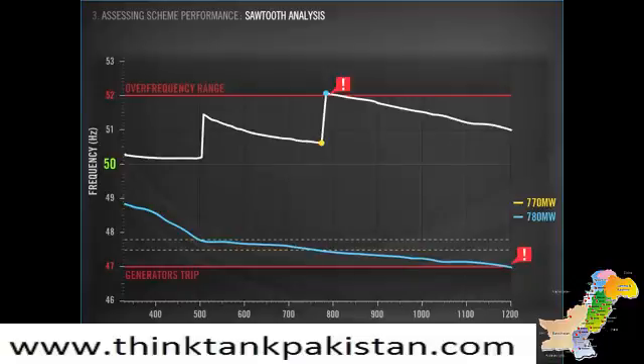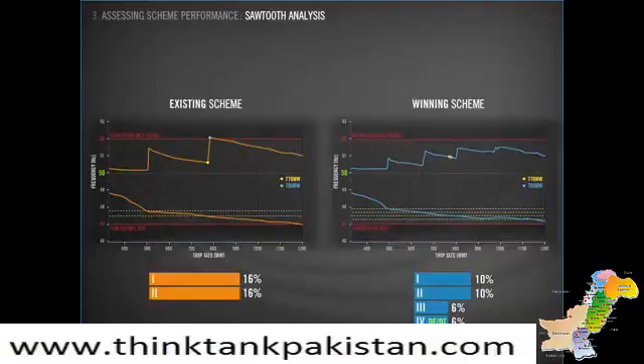With this new method of scheme analysis, we were able to compare the existing scheme with a range of scheme designs. We compared 6 in total. On the left, we have the existing scheme, with 2 blocks of 16%. You can see on the sawtooth that there are 2 points where the frequency goes outside the acceptable range. On the right is the winning scheme, with 4 blocks, 10, 10, 6 and 6%. Importantly, on the sawtooth you can see the results stay within the acceptable range. This comparison highlights what we have gained through changing the scheme. As you can imagine, there are many complex factors that contributed to this scheme design being chosen, and we will look at these next.